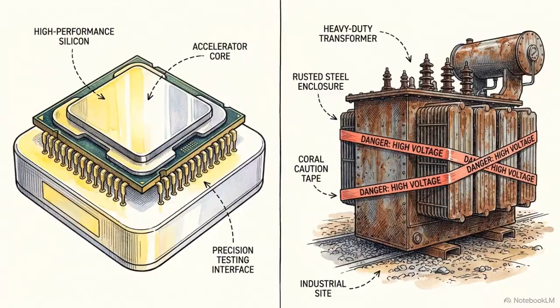Furthermore, the facility's redundancy models must match the primary load. Diesel generators and uninterruptible power supplies have to be drastically upsized to protect operations from grid fluctuations. Hardware budgets and procurement victories mean nothing if the site lacks the physical megawatt capacity to energize the racks.